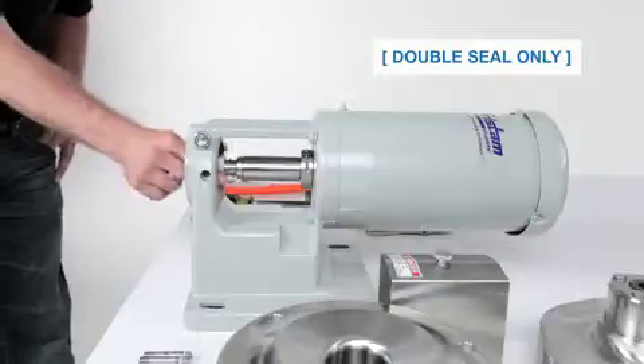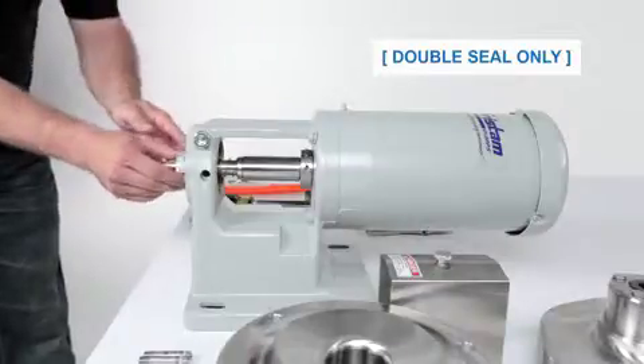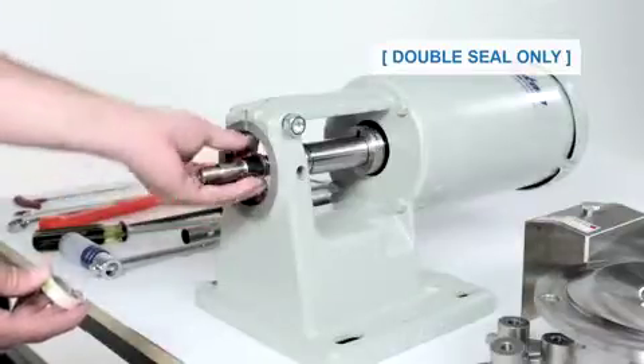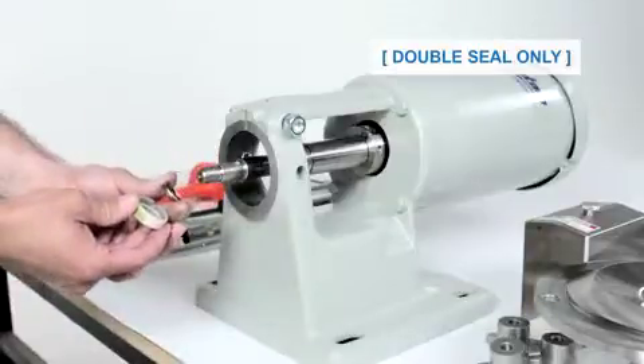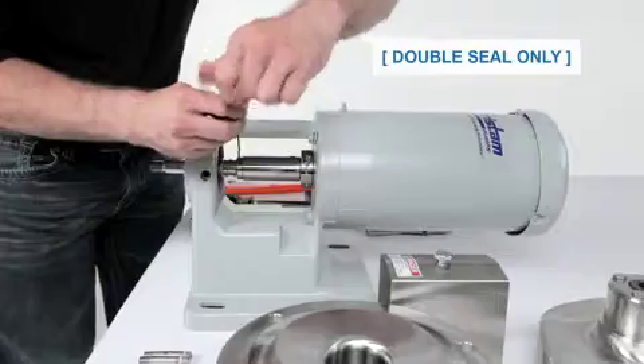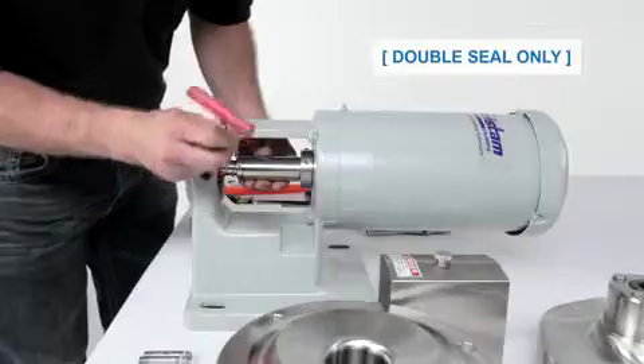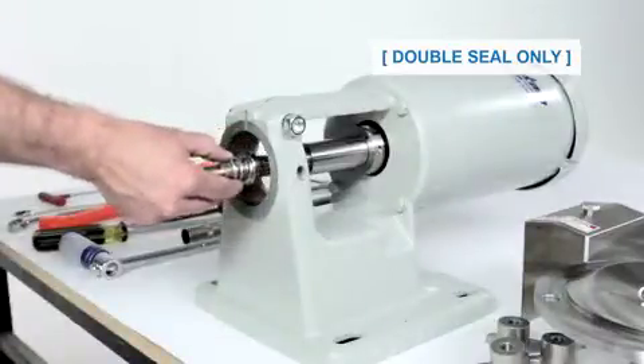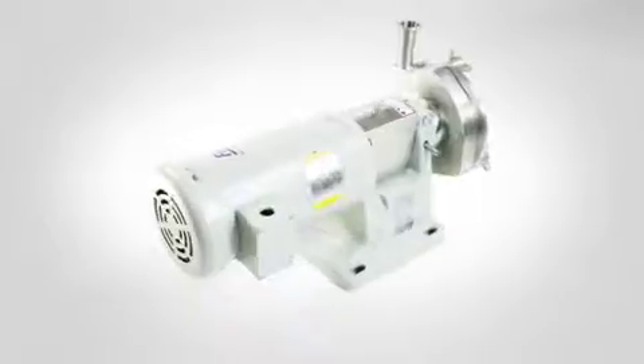To remove the rear seal components, carefully slide the rear rotating seal, seal washer, and seal O-ring off the pump shaft and discard. Then, remove the rear seal driver and spring off the pump shaft and discard.